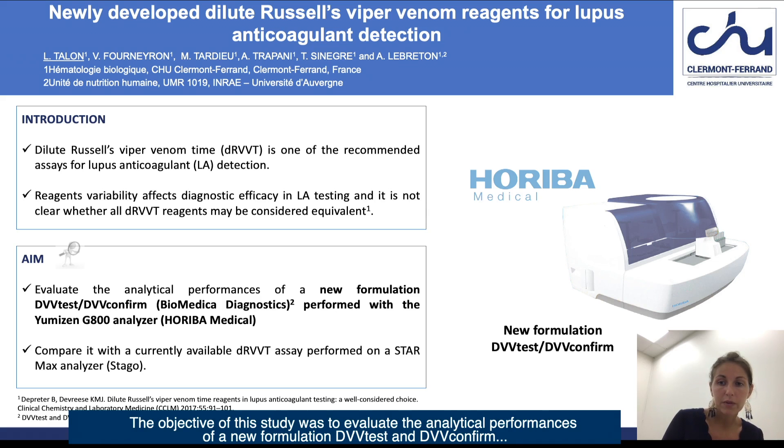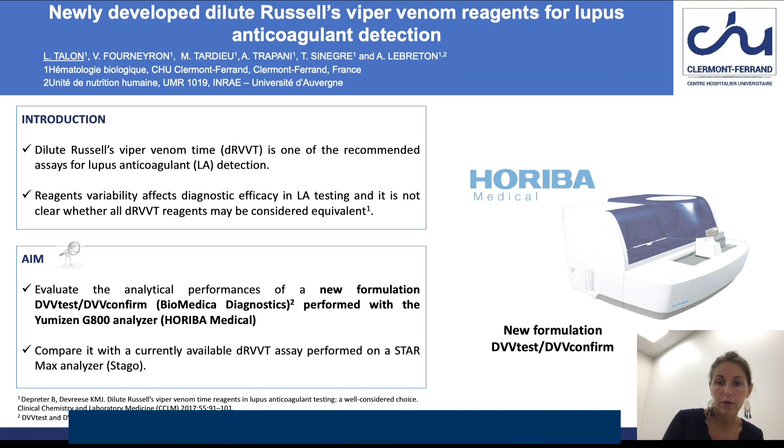The objective of this study was to evaluate the analytical performances of a new formulation DVV-Test and DVV-Confirm from HORIBA Medical performed with the Yumizen G800 analyzer, and to compare it with a currently available DRVVT assay performed on a StarMax analyzer from Stago.